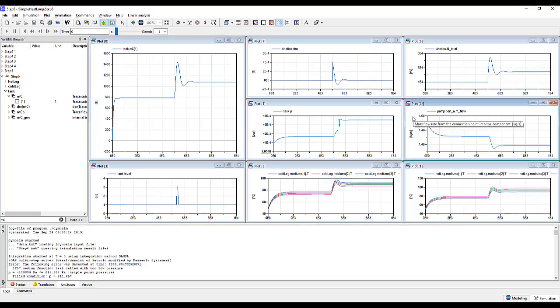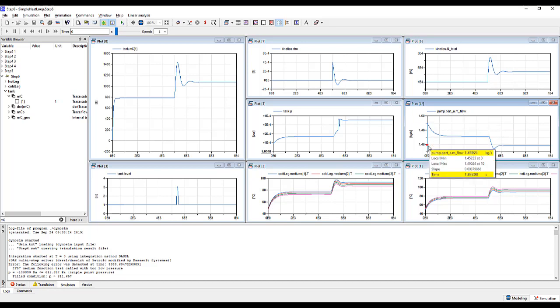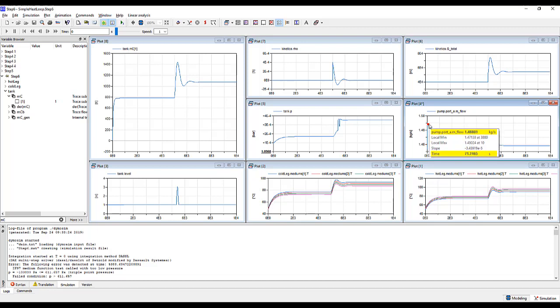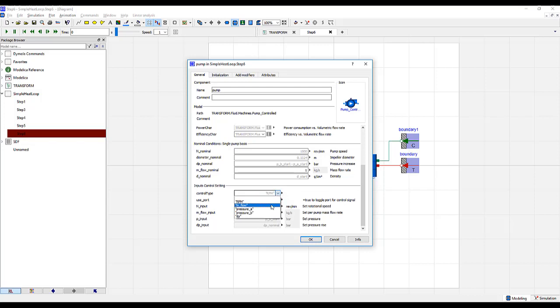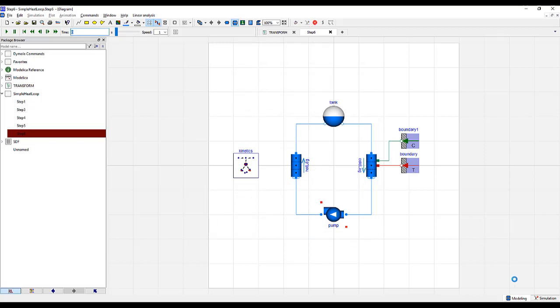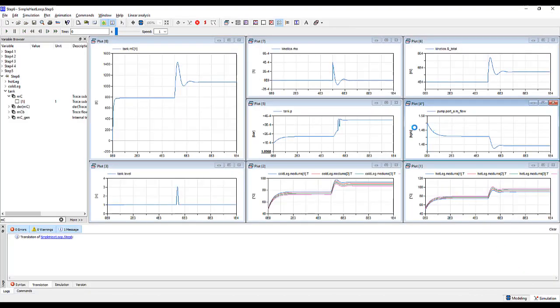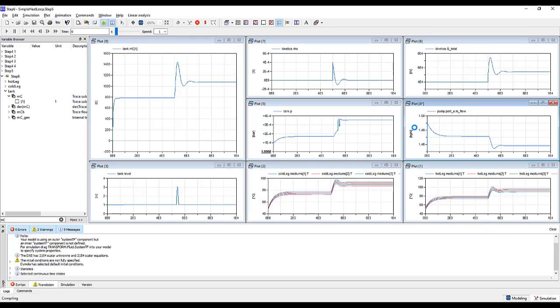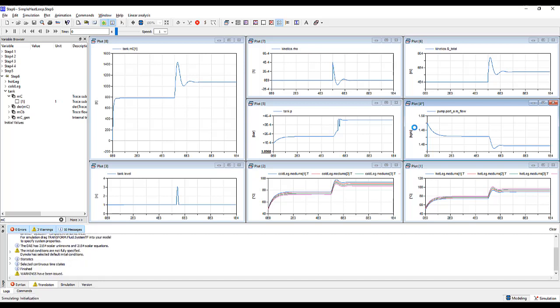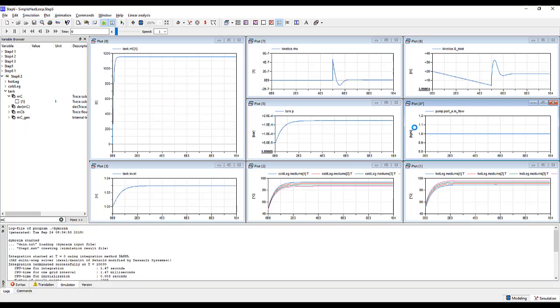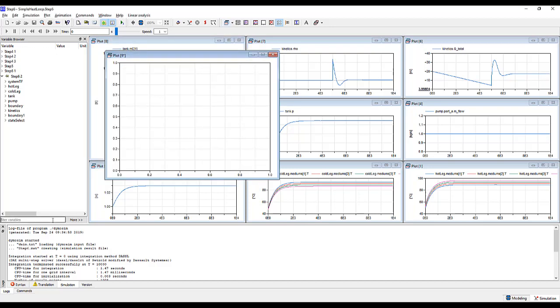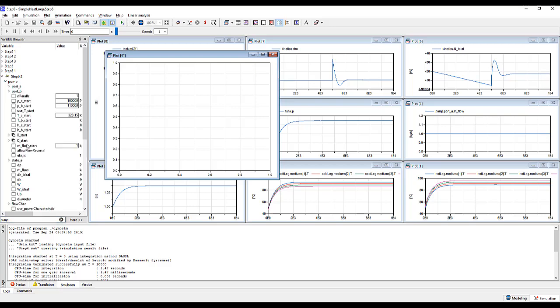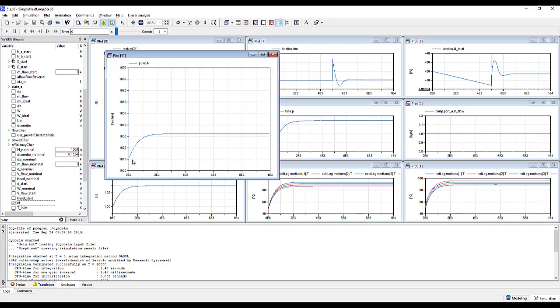Our results are significantly different. Why is that? If we look at the flow rate from the pump, we shall see that it is no longer held constant 1 kg per second, but instead starts at a value closer to 1.5 and has various oscillations. If we go back to the model, if we double click the pump and scroll to the bottom, we will see inputs for control settings, and see that currently it is controlled in RPMs. Let us go ahead and switch that to mass flow rate, and push OK, and re-simulate. Our results are now back to what they were before with a constant mass flow rate of 1 kg per second. Since the mass flow rate is constant, something else must have changed. Let's create a new plot and search for pump. Within the pump component, we will search for the variable n, which stands for the rotational speed of the pump. The rotational speed of the pump changed in accordance with the physics that were occurring in the system, resulting in a constant mass flow rate.